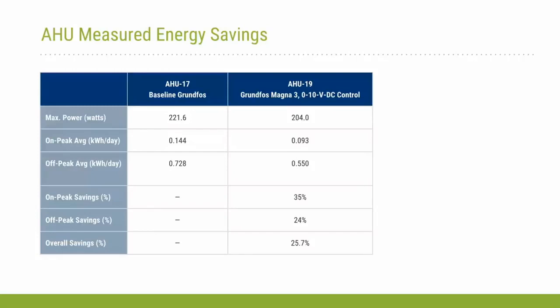And so really the savings that are achieved are when the pump is allowed to ramp up and down to meet the load. And in this case, since the pump only ran for a few hours a day, it ran at a higher speed than the domestic hot water pumps. So you'll see that we got a 35% on-peak savings, 24% off-peak savings, with a 25.7% overall savings. Okay, next slide.